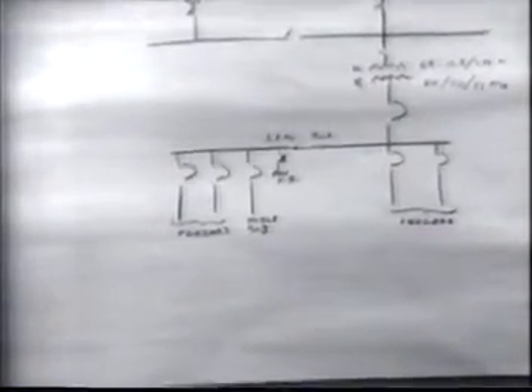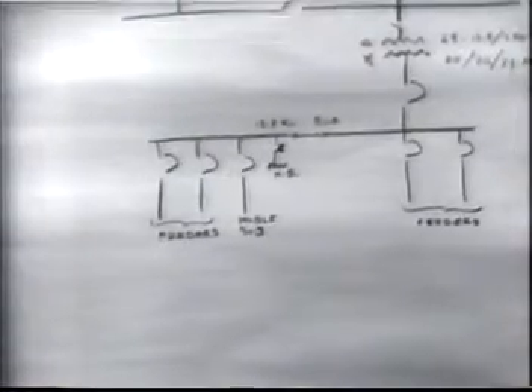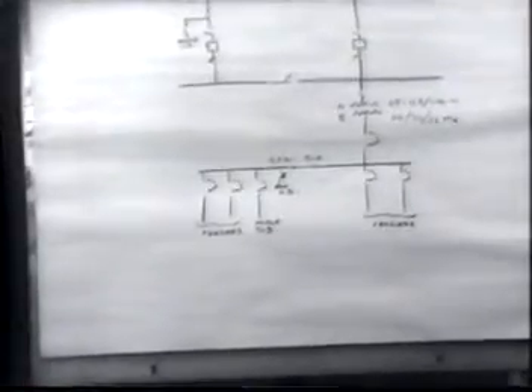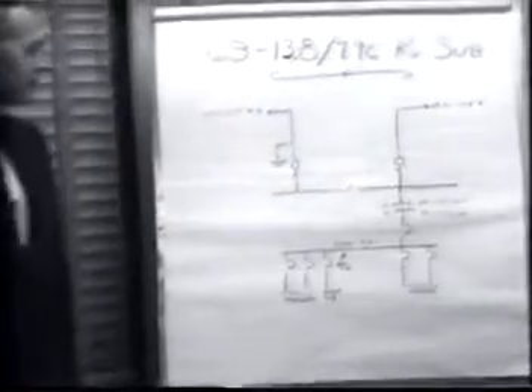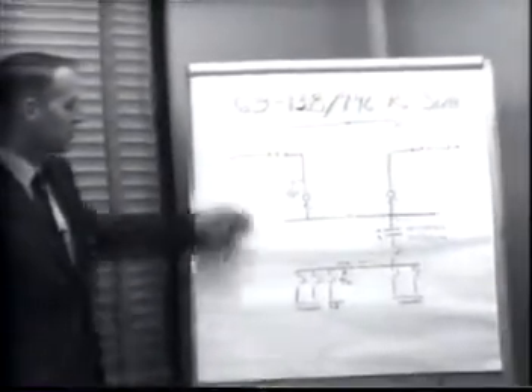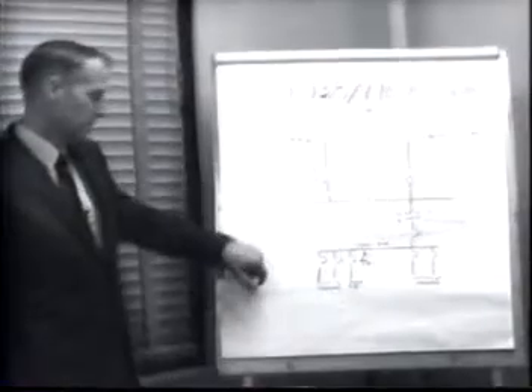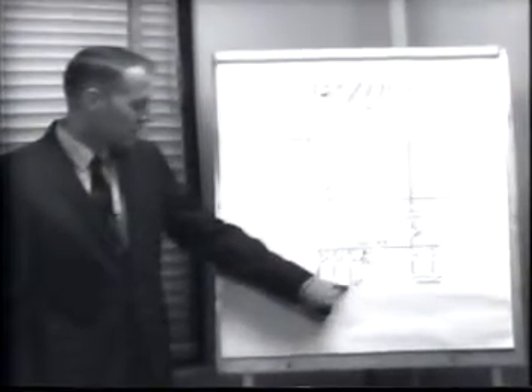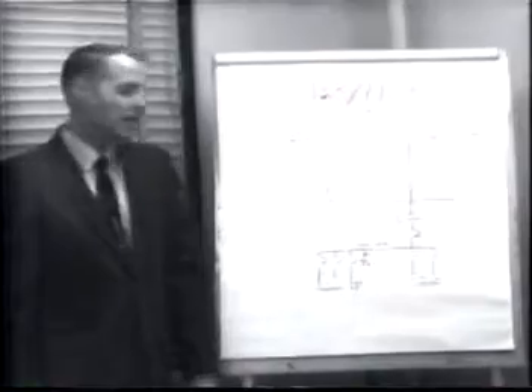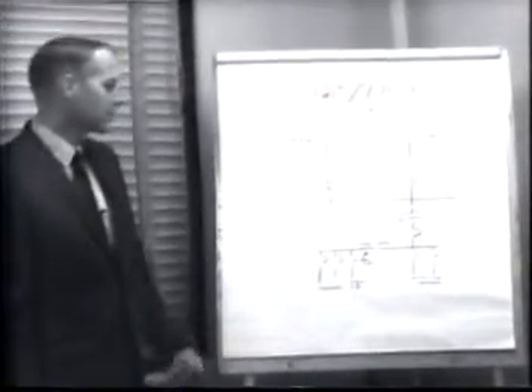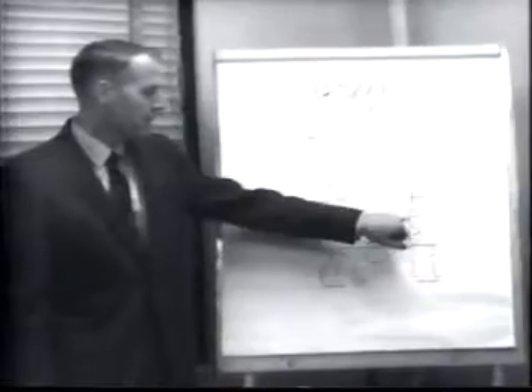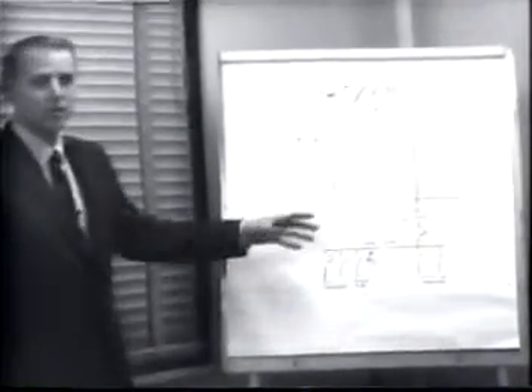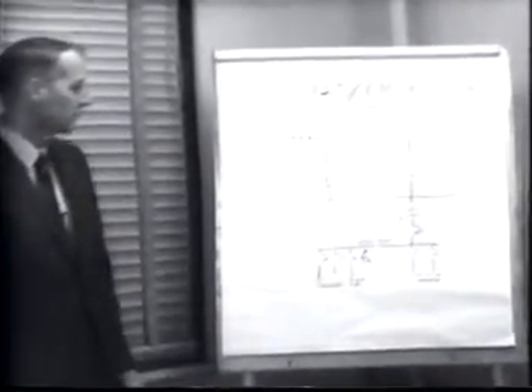So starting in 1958, we purchased a complete mobile substation. Our first one had a capacity of 12,000 kVA, and in a given substation we have provisions for connecting the 69 kV side of the mobile substation to a 69 kV line. The 13 kV side is connected to the 13 kV bus. This allows us to completely bypass the entire 69 kV structure and the transformer to allow maintenance or construction in these areas.